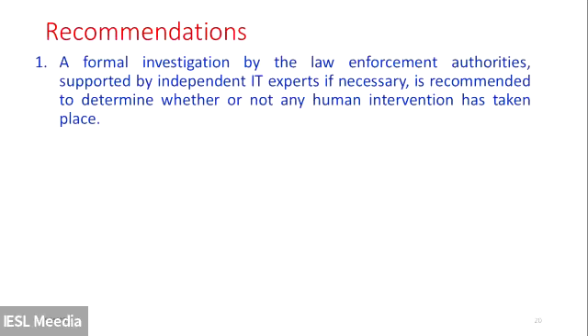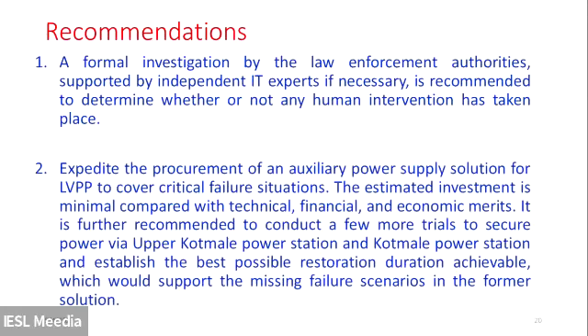But anyway, the end-fault protection took place. So we were not sure whether the earth fault took place accidentally and the end fault operated. If somebody knew that logic, okay, I can trigger the end fault if I create an earth fault. That's there. So we wanted to make sure and clear the CB that it is not the case, or it is the case, whatever it is. So we made the first recommendation.